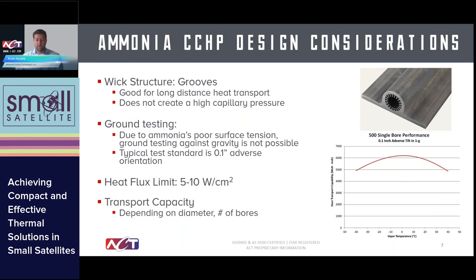We have a curve showing a half-inch diameter pipe, and we traditionally quantify capability in heat transport — referred to as watt-inches — from which you can back-calculate how much wattage your heat pipe can move based on pipe length. We have a standard set of extrusions in our catalog. If you're looking to design ammonia-based pipes into your system, feel free to email us afterwards. We offer our extrusion catalog of already-developed, proven, and flight-tested extrusions.